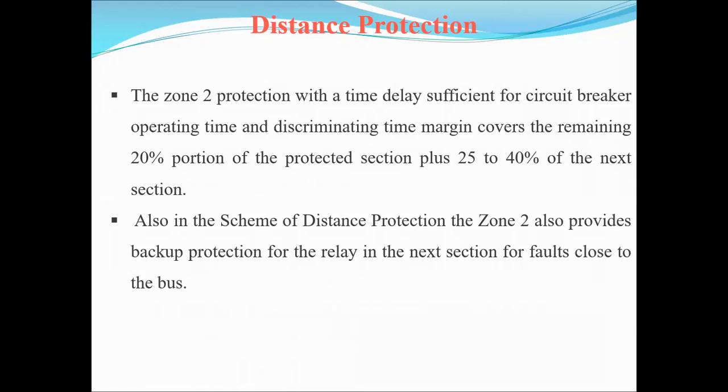In this type of distance protection, zone 2 also provides backup protection. Why is it called backup protection? Because it gives 25 to 40% protection for the next section. That's why it is called backup protection.